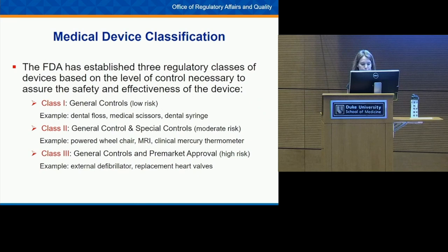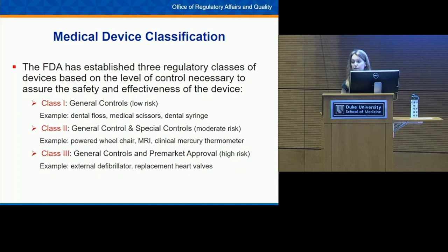Class III devices are the highest-risk devices — things critical for keeping a patient alive or diagnosing a condition, such as an external defibrillator or a replacement heart valve. For these, general and special controls are not sufficient, so in addition to general controls, Class III devices require pre-market approval before going on the market.